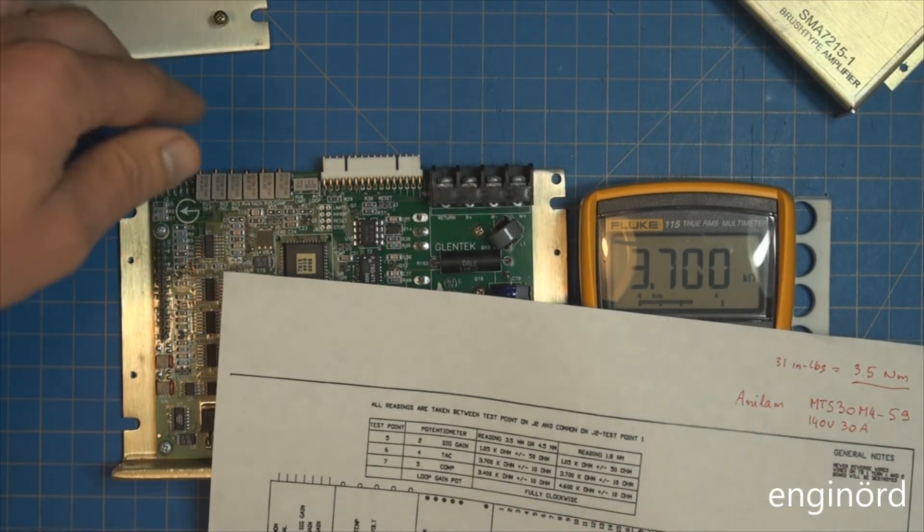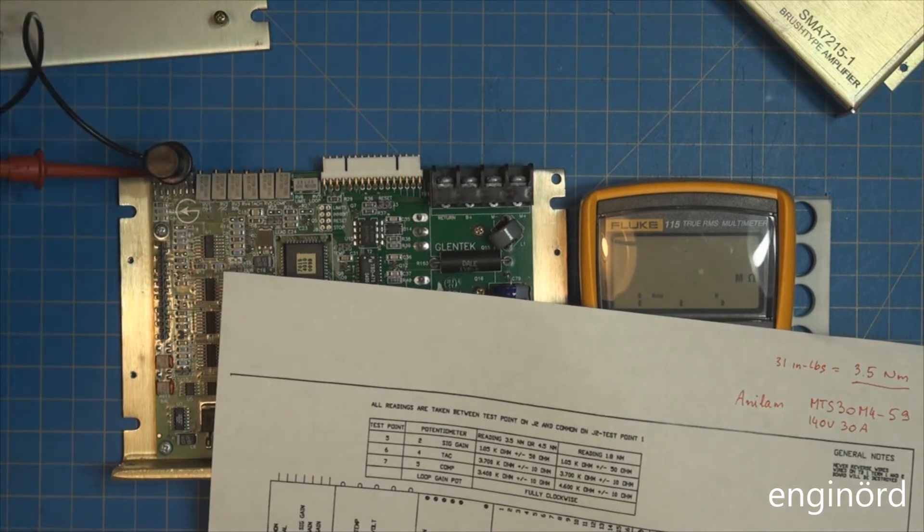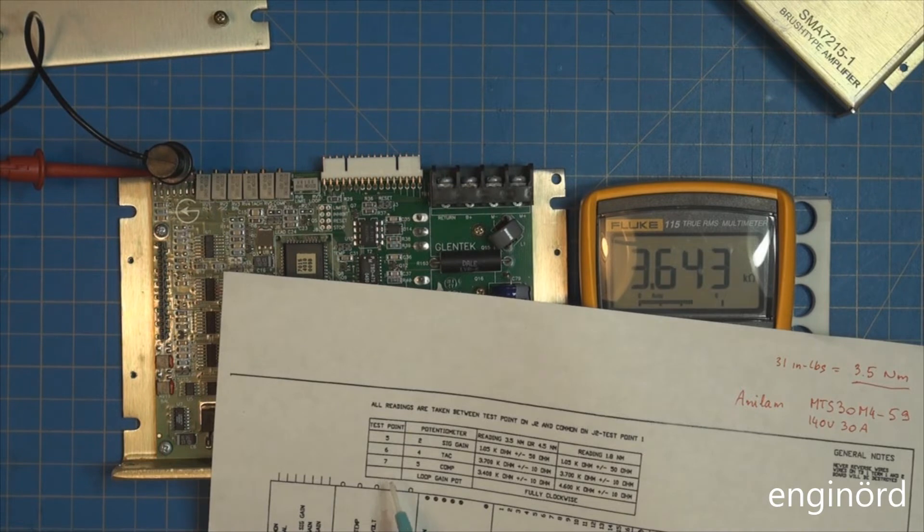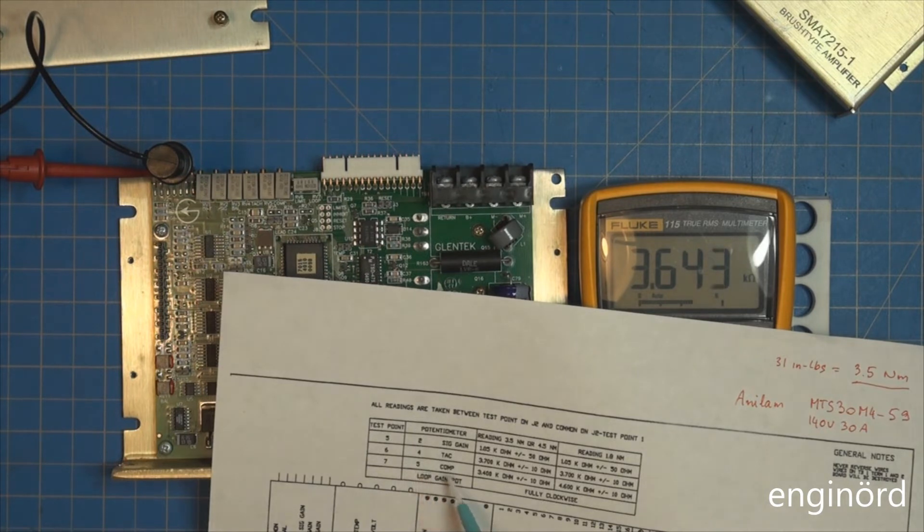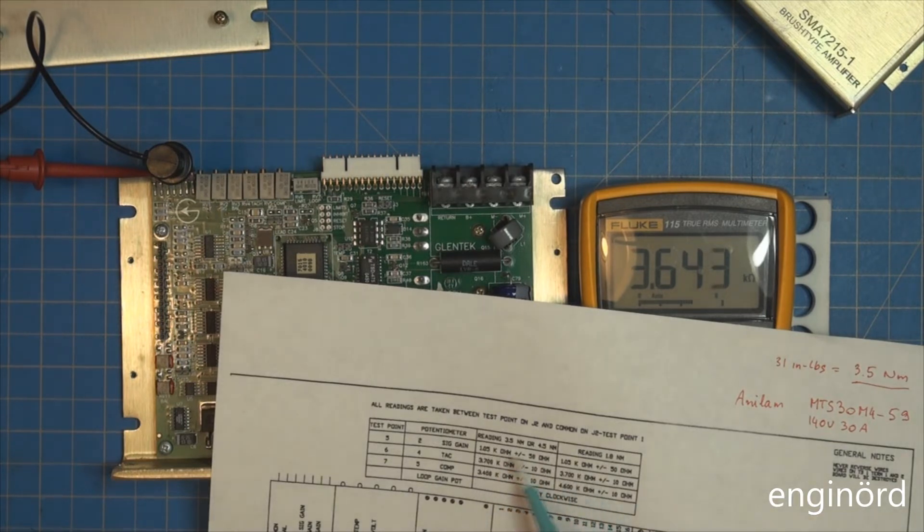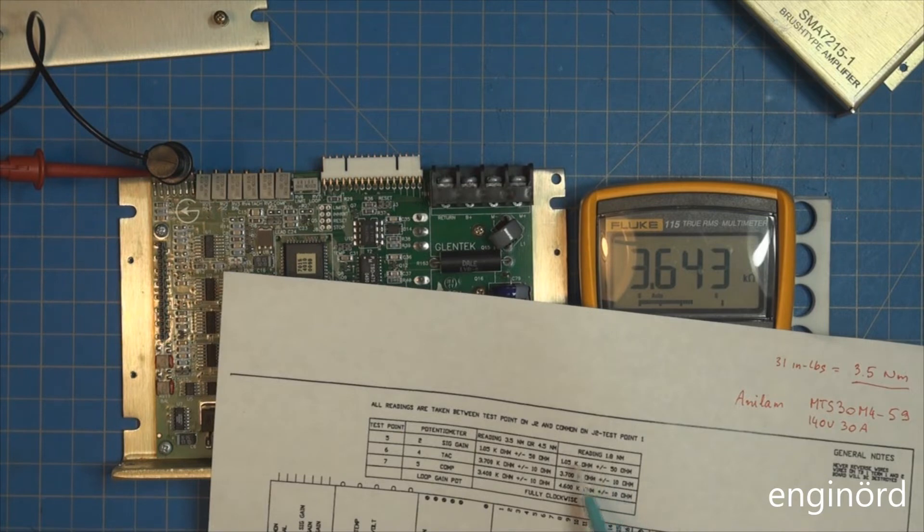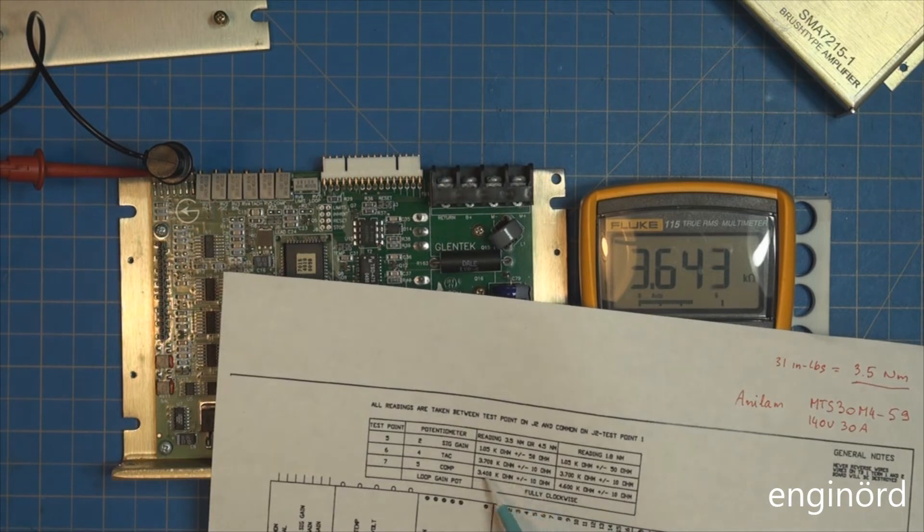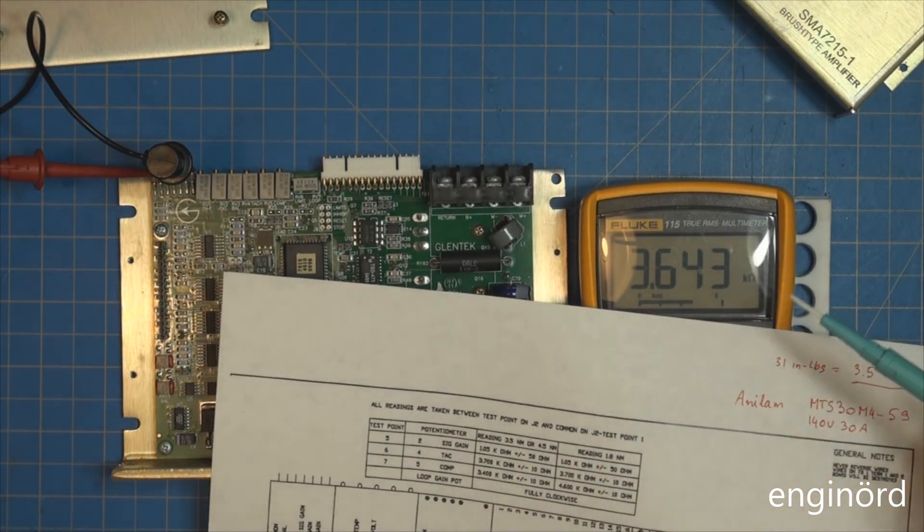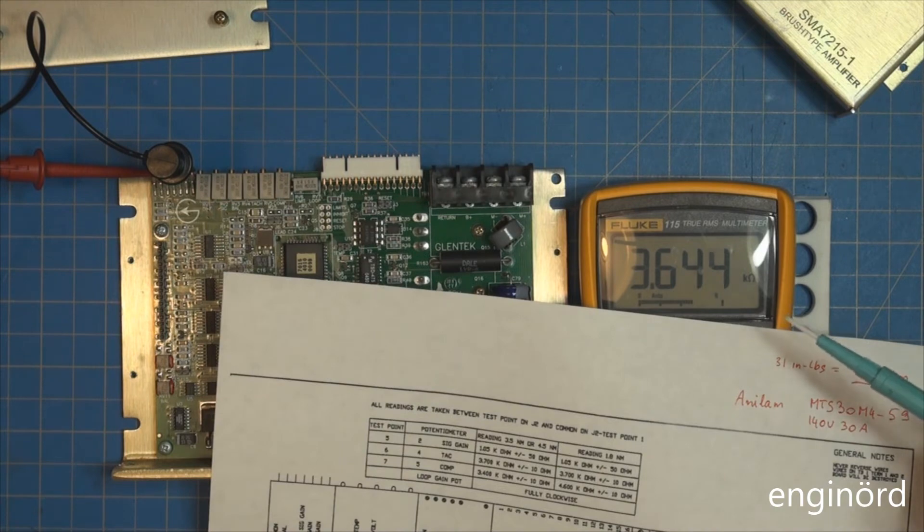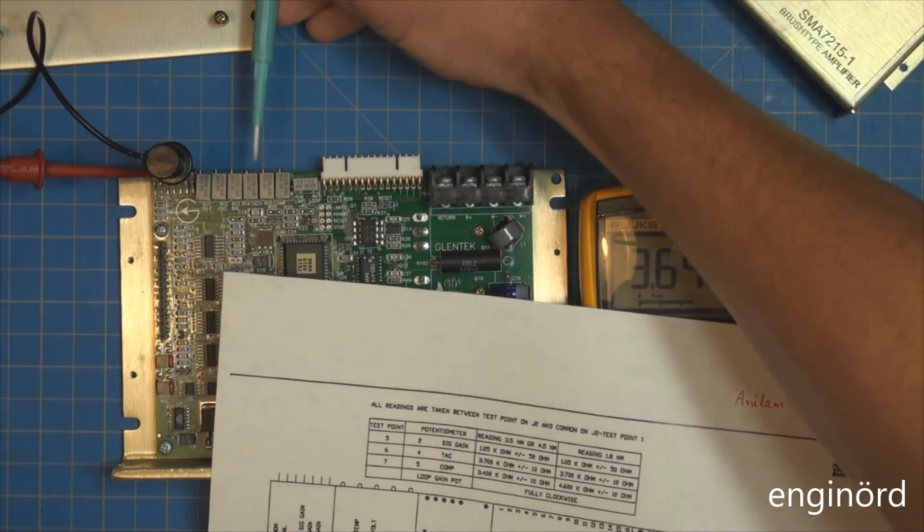The last one is number 7 test point, and it's potentiometer number 5. It's supposed to be 3400. If you look at the numbers here, you can see the difference between the 3.5 and the 1.8 newton meter motors is this one - that's the compensation. Right now it stands at 3600, so I'm going to bring it down to 3400. 3401, is it good enough? We will see.